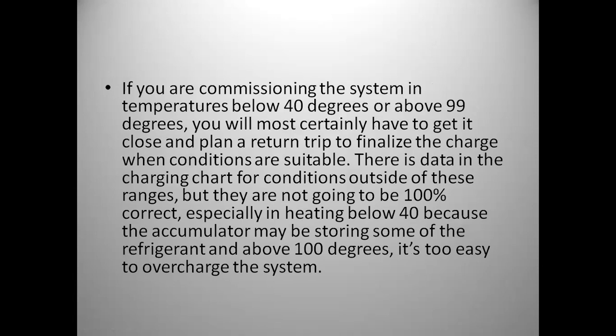Now, if you are commissioning the system in temperatures below 40 degrees or above 99 degrees, you'll most certainly have to get it close and plan a return trip to finalize the charge when conditions are more suitable to the chart. There is data in the charging chart for conditions outside of these ranges, but it's not going to be 100% correct, especially in heating below 40, because the accumulator may be storing some of the refrigerant. And above 100 degrees, it's way too easy to overcharge the system.